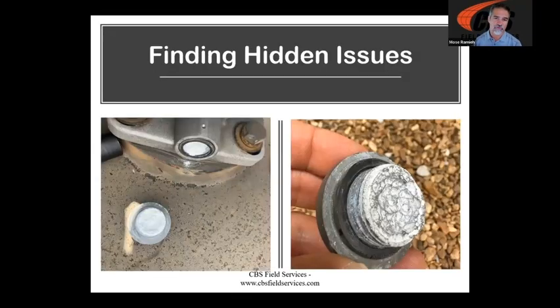The other thing is that by doing a little bit more, by doing the bushing test, you'll also find hidden problems. This was not a problem we expected to find. For those that maybe know transformers, this is what's called the capacitive tap test point. This is how we test a bushing. We remove this cap, and then there's a connection point in here where we can test and get information about our bushing, like I just showed you. Well, sometimes these caps don't get put together properly, and they can begin to arc and deteriorate and cause damage. You can see the erosion in this cap right here.